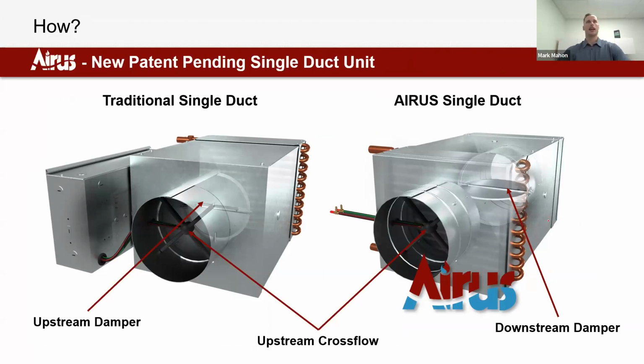It's patent pending. It looks very much like a normal single duct box, intentionally so. But what the Airus does is it just recontextualizes and repackages the major components to overcome this design issue. And what we've done is we can see here, we've moved the damper downstream of the heat exchanger. We've moved the heat exchanger up to the front end of the box. And we've still maintained the cross-flow sensor in the inlet portion of the unit, which is really critical to make sure we measure and control airflow properly.